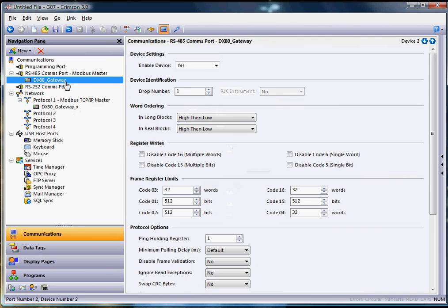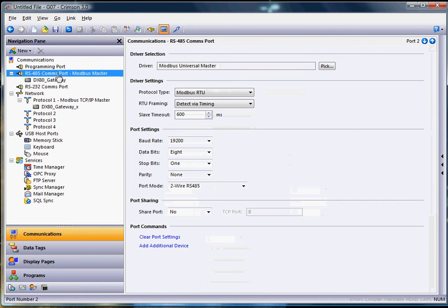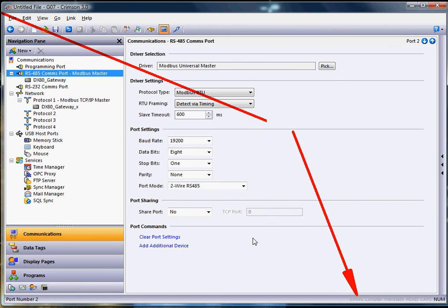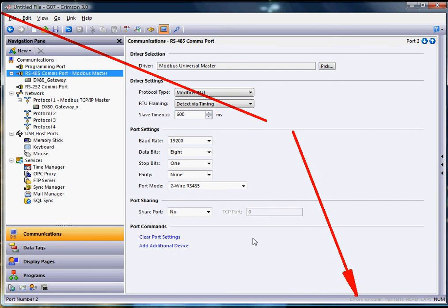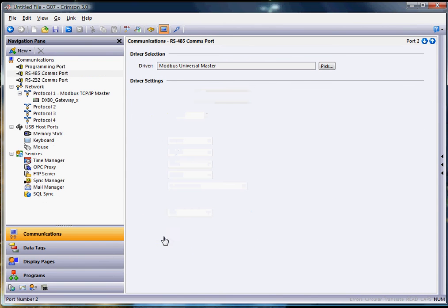So what I'm going to do is I'm going to go up here to the DX80 gateway and I'll click on the RS485 COM port, the header right above that's the driver selector, and I'm going to click the clear port settings down here. Now folks, I want you to take note, look down here in the screen right here, there's a little section that says errors. When I click the clear port setting, we should have a bunch of errors. Let's see what happens here. Boom.